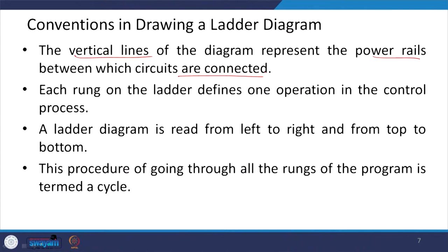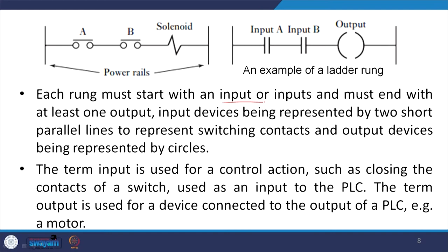Here are the conventions for drawing a ladder diagram. The vertical lines of the diagram represent the power rails between which the circuits are connected. Each rung on the ladder defines one operation in the control process. The ladder diagram is read from left to right and from top to bottom. Going through all the rungs of the program is termed a cycle. Each rung must start with an input or inputs and must end with at least one output.